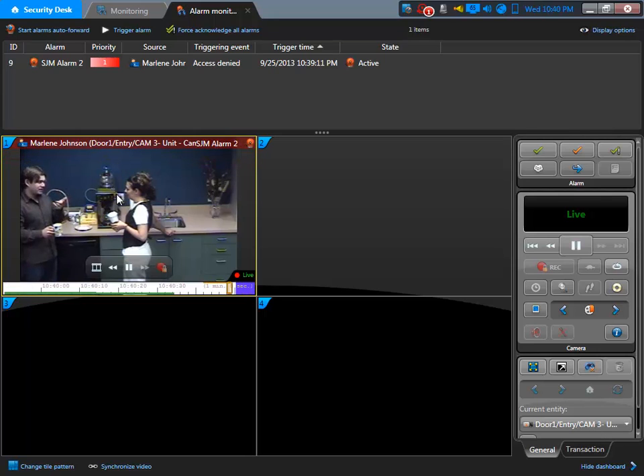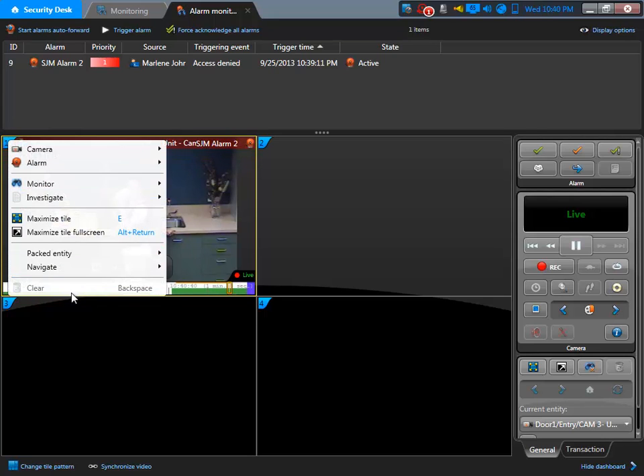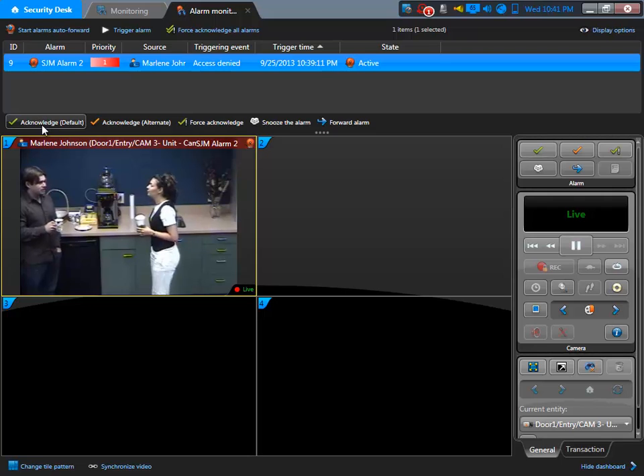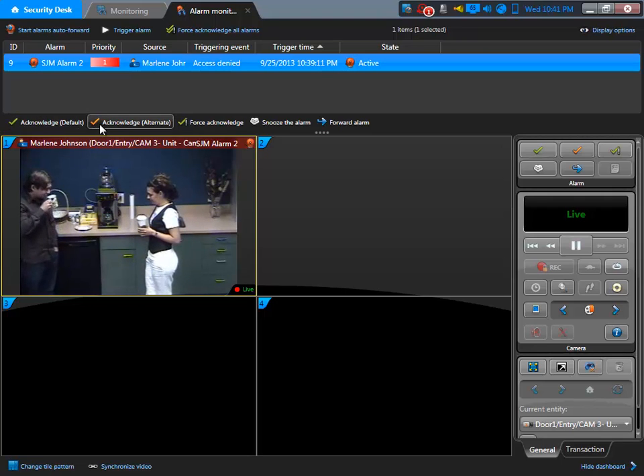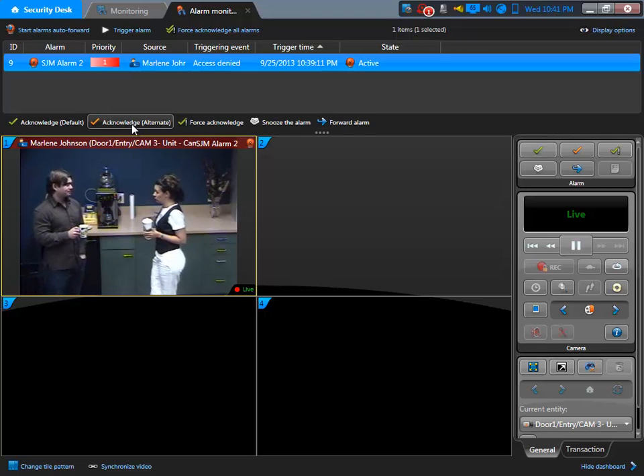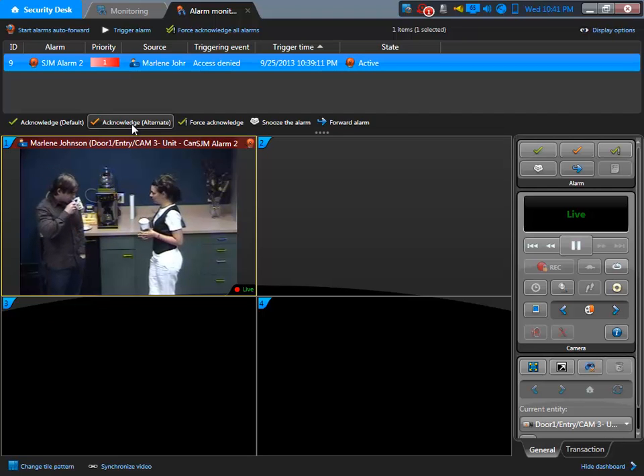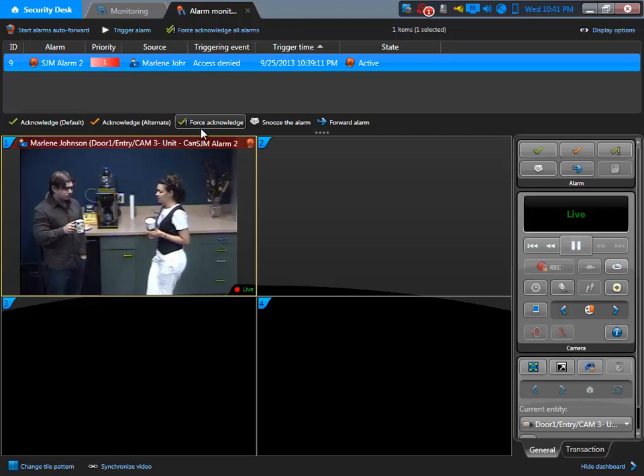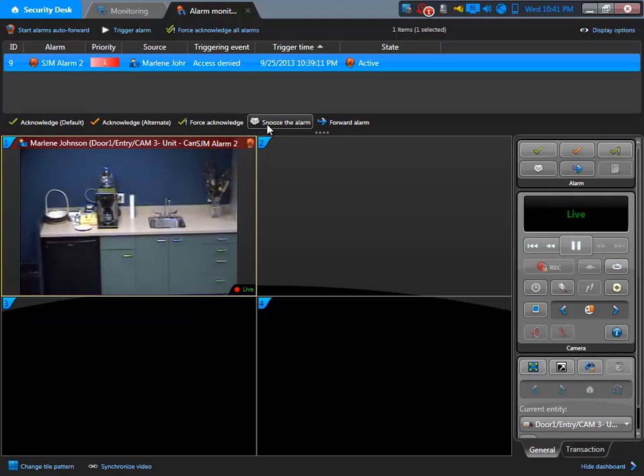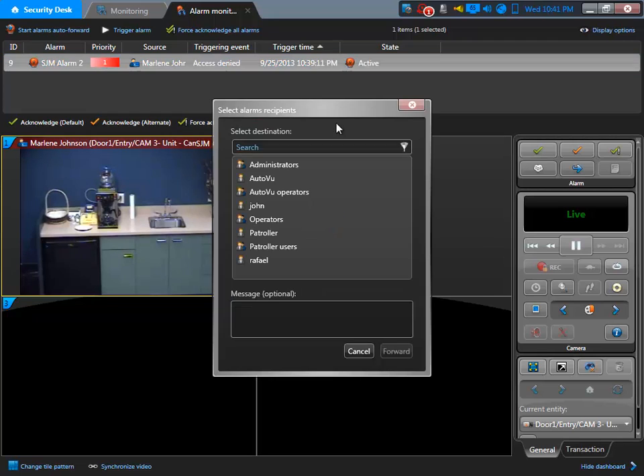We can also stop the cycling of the alarms, and we can clear that alarm. If we select the alarm at the top, we can acknowledge the alarm. We have the option to acknowledge, or use an alternate acknowledgement — for example, if we have false alarms, we can decide to clear that alarm as an alternate acknowledgement. We can force the acknowledgement, snooze the alarm for 30 seconds and it will appear again, or forward the alarm to someone else.